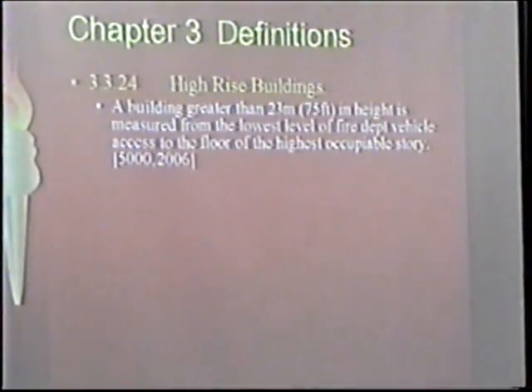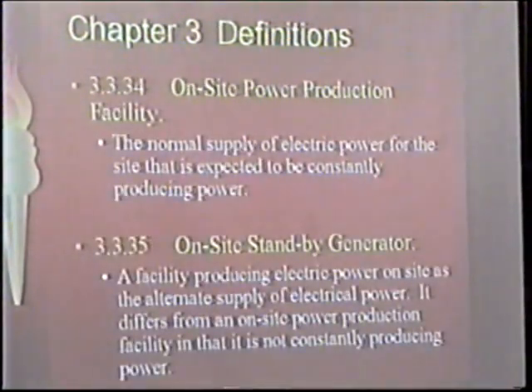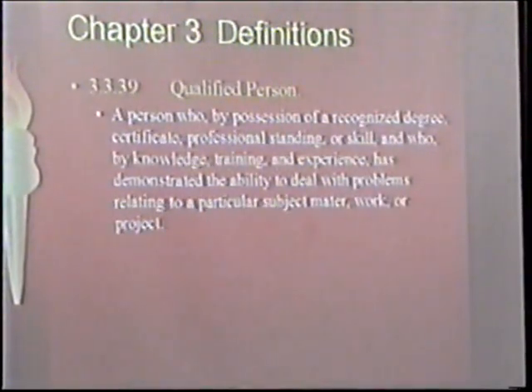They actually define what a high-rise building is in NFPA 20. I mean, there's nothing new here, but this definition had not been in NFPA 20 before. And here's what Dave was talking about a little bit earlier, is they define the power. Yep. Power supply, on-site production facility. So you are going to have your own power generation. It has to be constantly running, as opposed to a standby system that may not be constantly running. And here they got a definition for all of us.